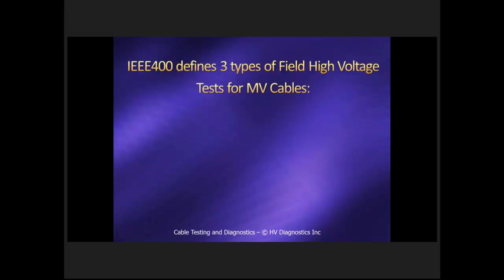The IEEE also defines three types of field testing. So that doesn't matter if you're doing a withstand test or a diagnostic test. They can either fall under installation test, which is done on a cable reel, for example, or before the installation of any accessories onto the cable, and obviously well before energization of the cable, followed by a commissioning test, which is done on the cable but before energization under the power frequency or under the grid. And finally, this is the one that a lot of us get involved in as well, is in the maintenance testing, trying to assess the condition of the cable during the life of that cable.